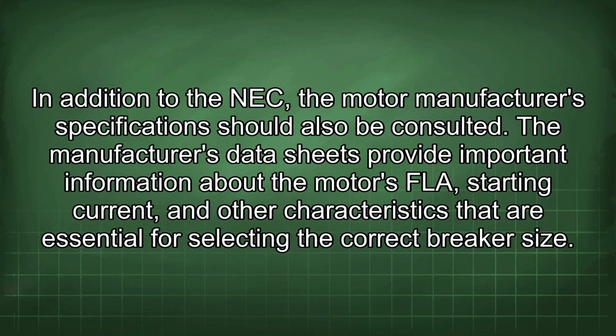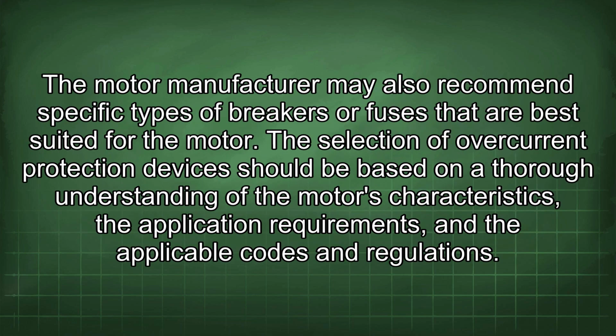In addition to the NEC, the motor manufacturer's specification should also be consulted. The manufacturer's datasheets provide important information about the motor's FLA, starting current, and other characteristics that are essential for selecting the correct breaker size. The motor manufacturer may also recommend specific types of breakers or fuses that are best suited for the motor. The selection of overcurrent protection devices should be based on a thorough understanding of the motor's characteristics, the application requirements, and the applicable codes and regulations.